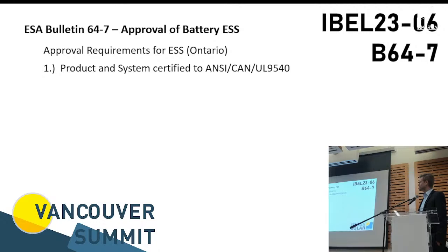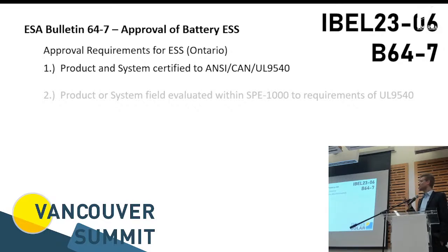The approval requirements for Ontario are slightly different than BC. If we sum that up, ideally the system is UL 9540 and UL 9540A certified and tested in the first place, because that gives you all the documentation that you can hand over to your inspector, and you're already 90% there. Versus if you have these field assembled systems, there's a lot more paperwork and you might be forced into a field evaluation, and things get complicated and costly very, very quickly.